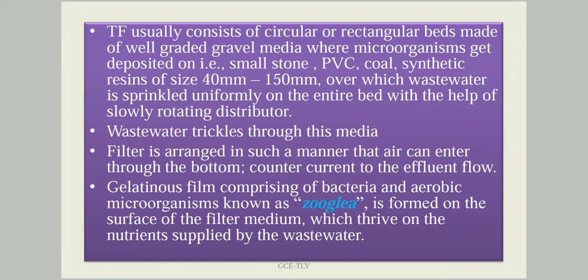The water is spread throughout the bed area by a slowly rotating rotary distributor. This wastewater trickles down through the media. The filter is arranged so that air can enter through the bottom, and we may supply additional air through the medium counter-current to the effluent flow direction. As a result, there is formation of a gelatinous film comprising bacteria and aerobic microorganisms, together called zoogloea, formed on the surface of the filter medium.